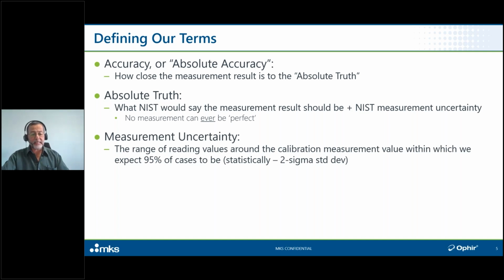What we call in the data sheets measurement uncertainty is the range of reading values above and below the calibration measurement value within which we expect, and here's a bit of a funny bit, 95% of cases in the case of Ophir to actually fall. In other words, it's a confidence level when we say that the accuracy of this instrument is, let's say, plus minus 3%. Why am I talking about confidence level? Because as we're going to see over the next few minutes, everything here really revolves around statistics. In Ophir data sheets, we always base everything on a 2 sigma standard deviation. If you don't know what on earth I just said, don't worry about it. But those of you who do know what I said will appreciate the meaning.